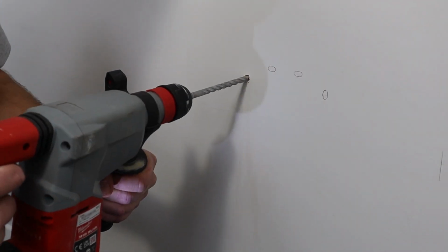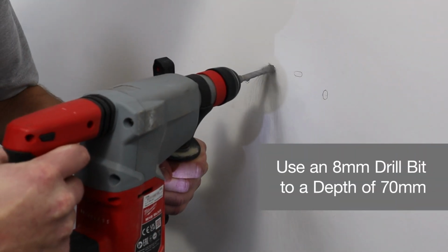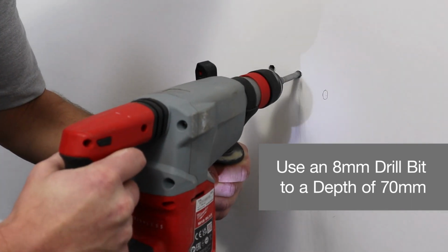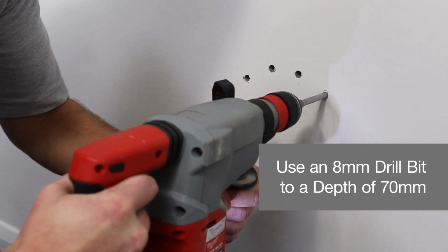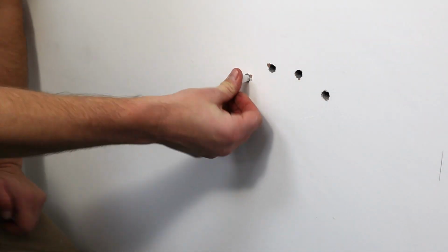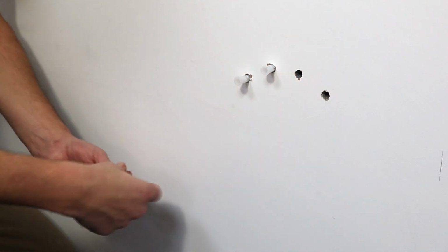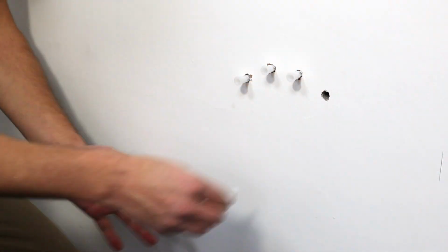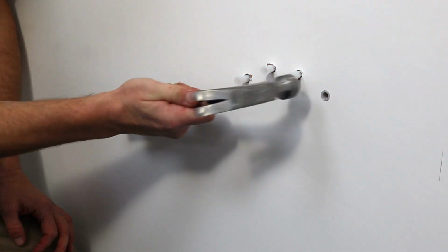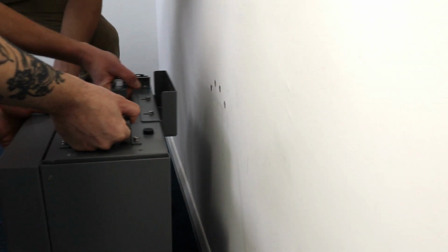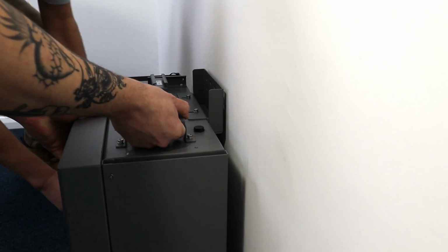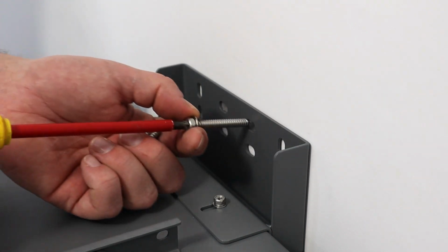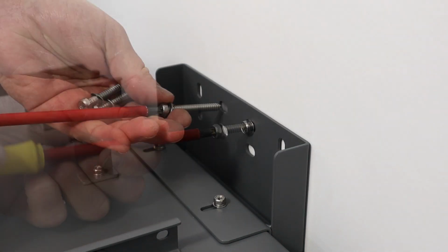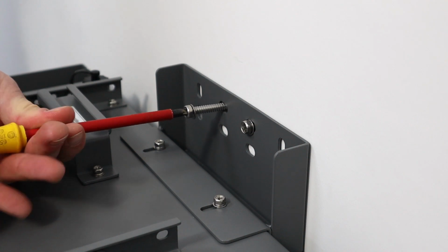Remove the battery to one side and drill the holes for the mounting screws. For this, you will need an 8mm drill bit and drill each of the 4 holes to a depth of 70mm. Insert the supplied rawl plugs and ensure that they are tapped flush. Move the battery back into position and secure the bracket using the supplied fixing screws.